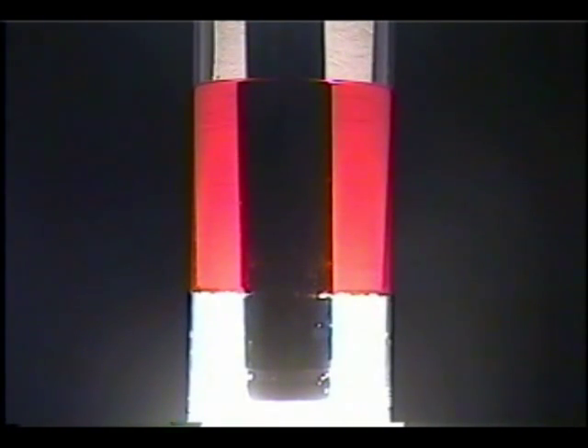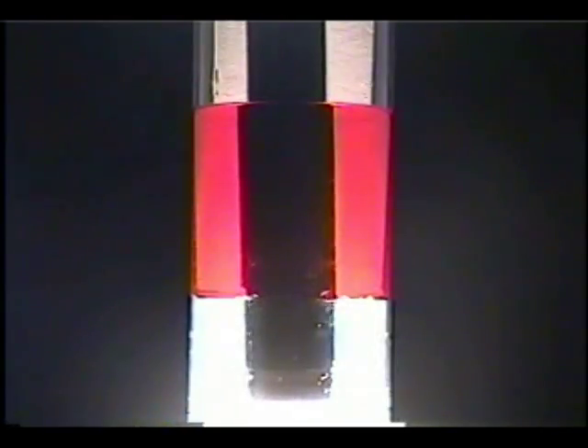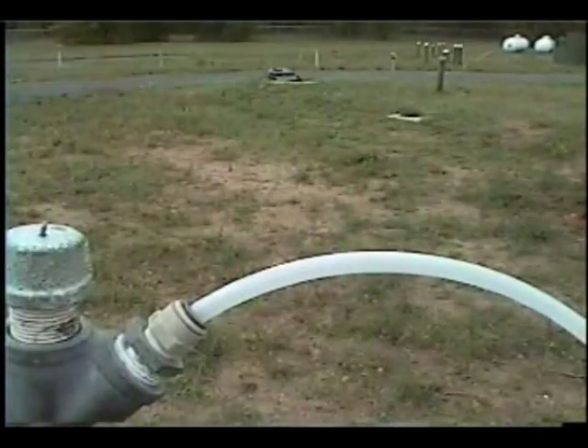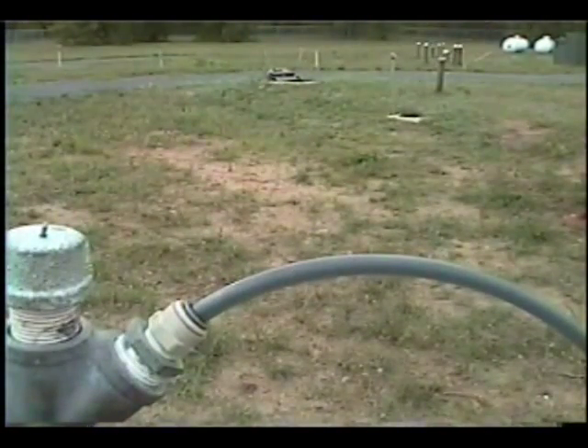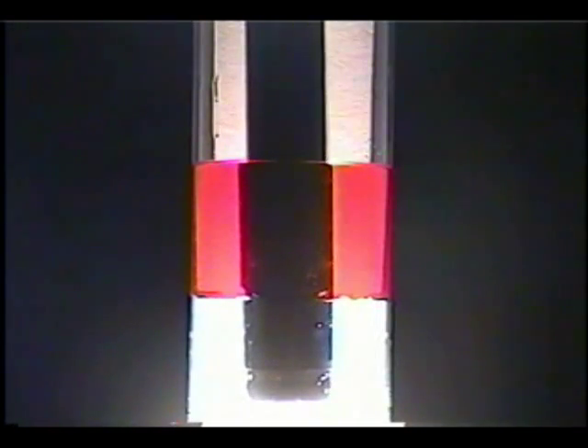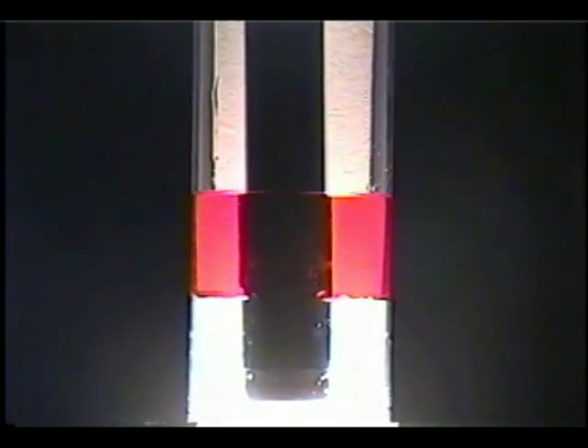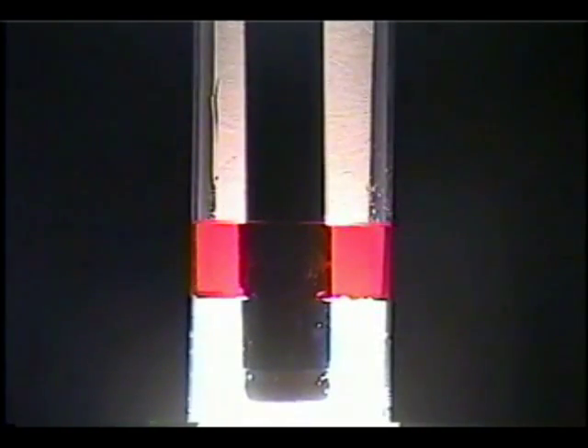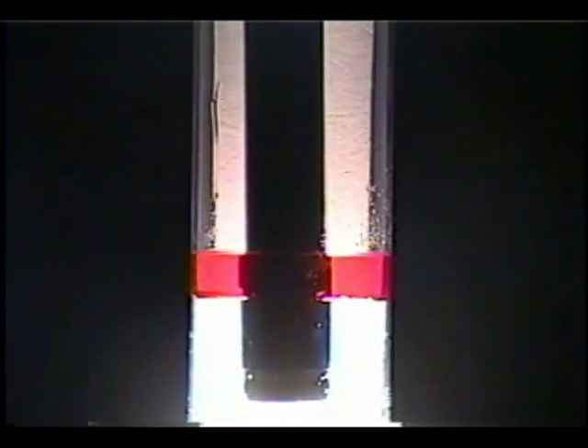The product will then begin to be pumped to the surface at the rate of 3/4 of a gallon or 3 liters per minute. The pumping of the product will continue until there is only 1/8 of an inch or 1/2 centimeter left in the well. The system will then go into a delay mode until the product has had time to recharge into the well. The system will then begin a new cycle.